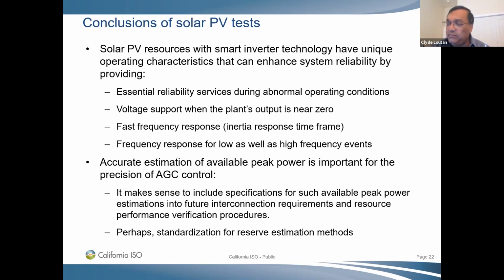Now, it's not a requirement from the California ISO to smoothen out that curve, because what we look at is, similar to a wind plant, geographic diversity minimizes variability. So with a couple of plants, the variability could decrease. Sometimes it increases. So there's no set requirement that each solar plant needs to install storage. The reason they install storage now is to qualify for tax credits and other incentives, but not from an operational standpoint. You do not really need storage to partner with solar. Mm-hmm.